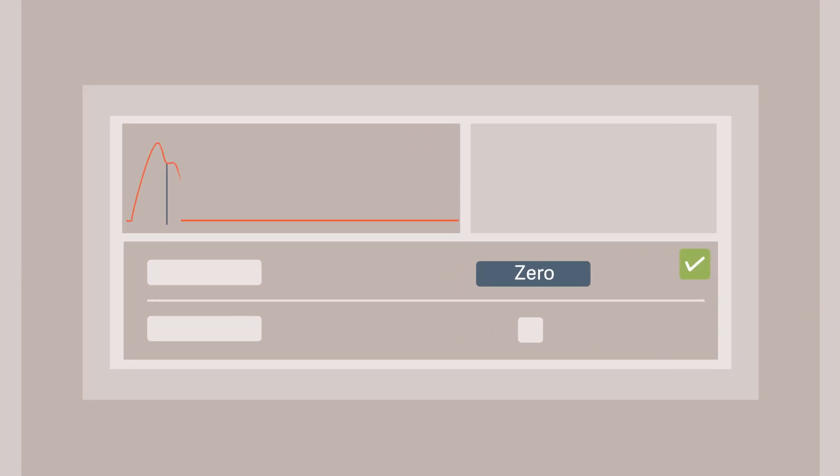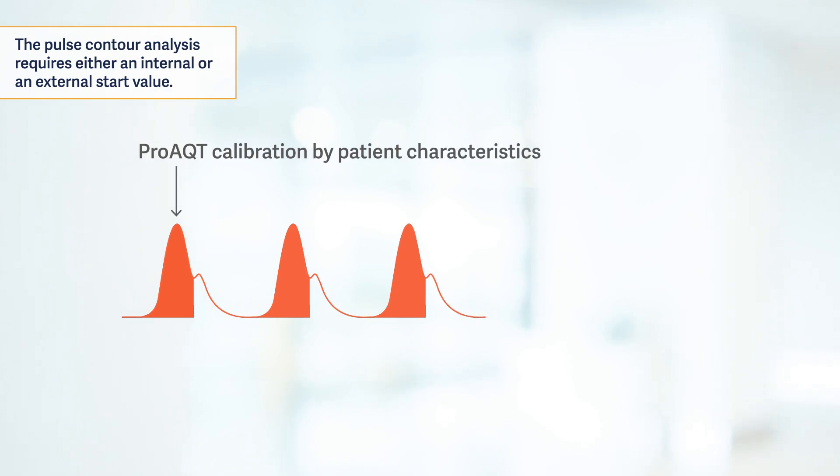The pressure curve reappears on the monitor. Finally, enter the Current Central Venous Pressure, or CVP, for Systemic Vascular Resistance Index, or SVRI, calculation. Note that the pulse contour analysis requires an internal start value based on the patient characteristics and details of the arterial pressure curve, or an optional input of an external start value, such as a measured CI value from an external source, for example, echocardiography.